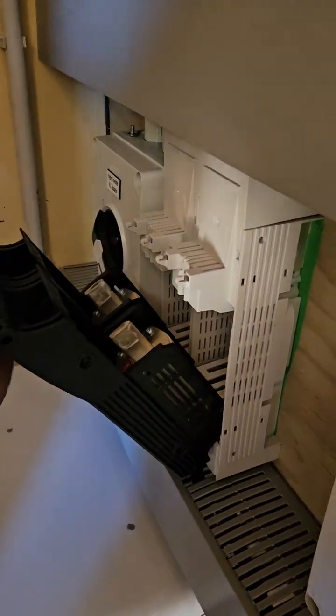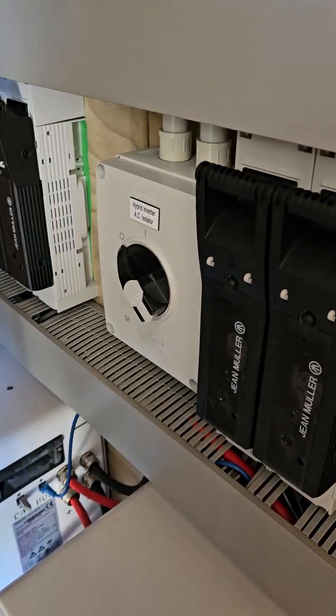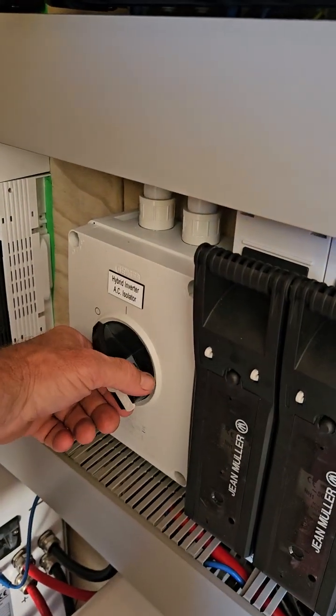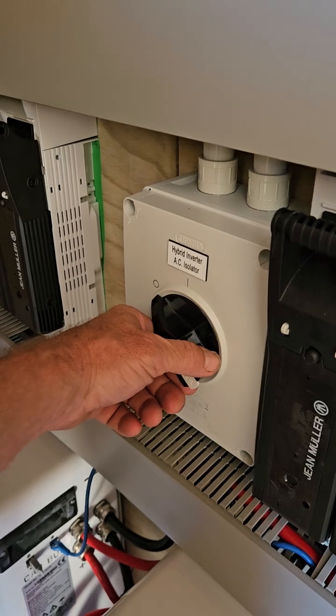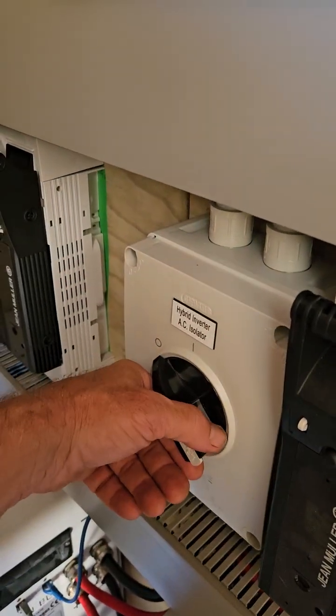So you've got power on the DC bus. Now I've closed the DC isolation. You want to do that nice and fast because it is DC current, which can cause arc flashes.